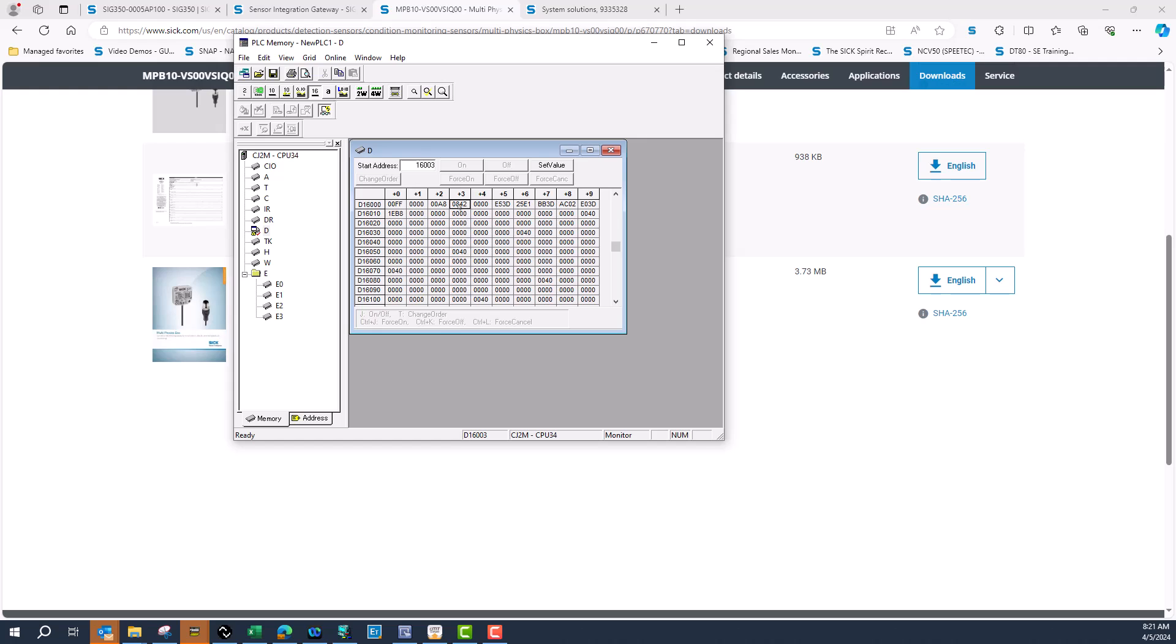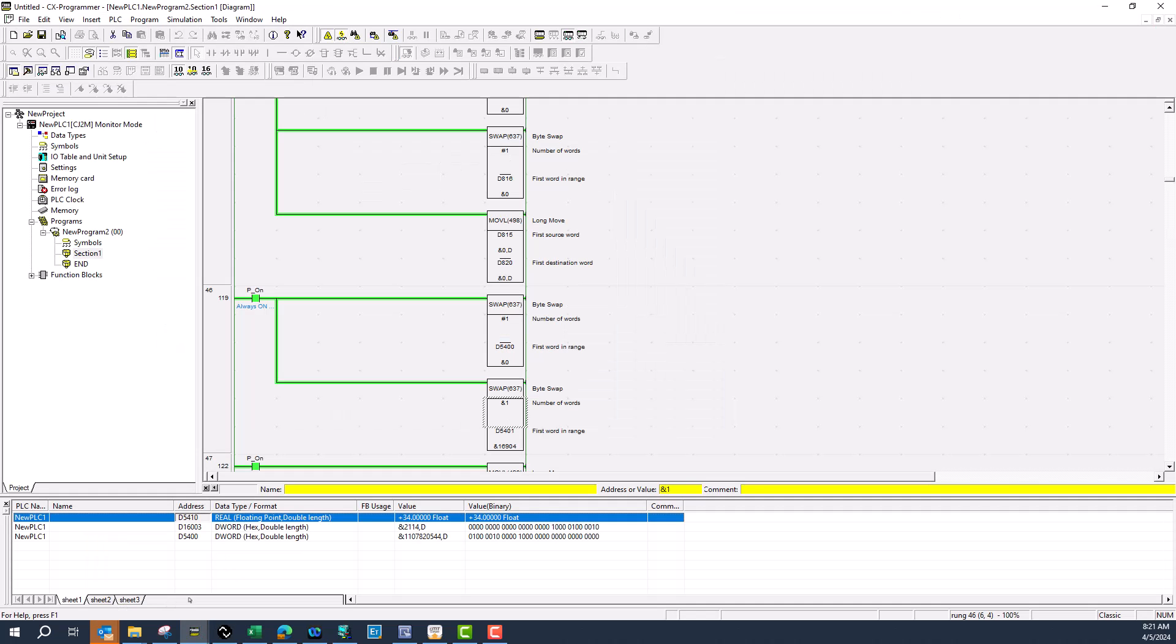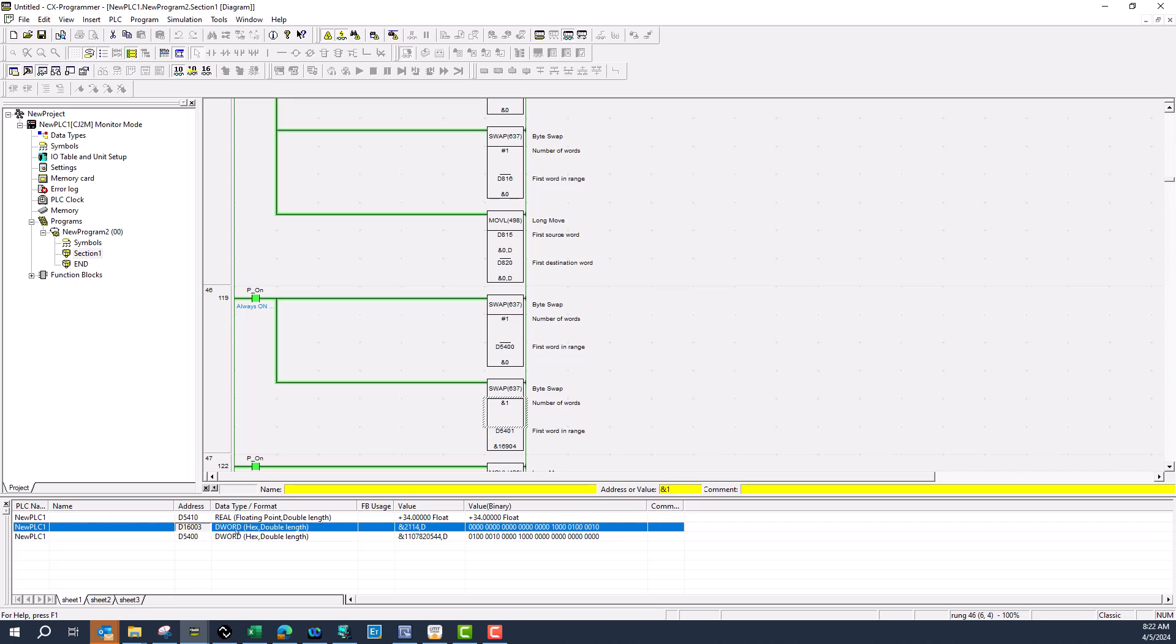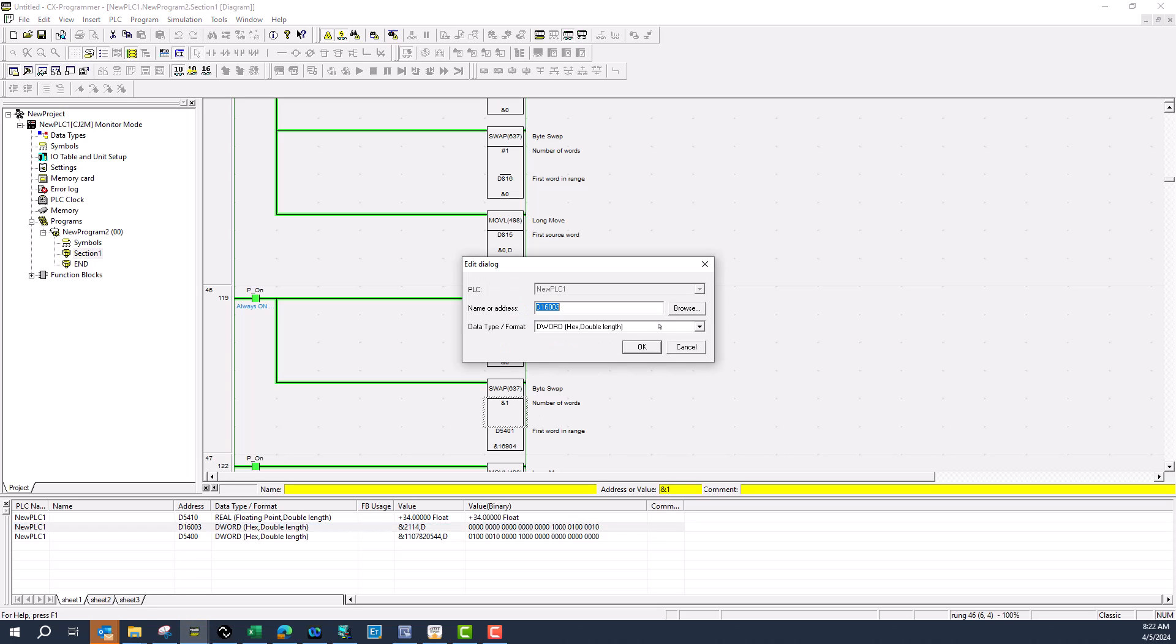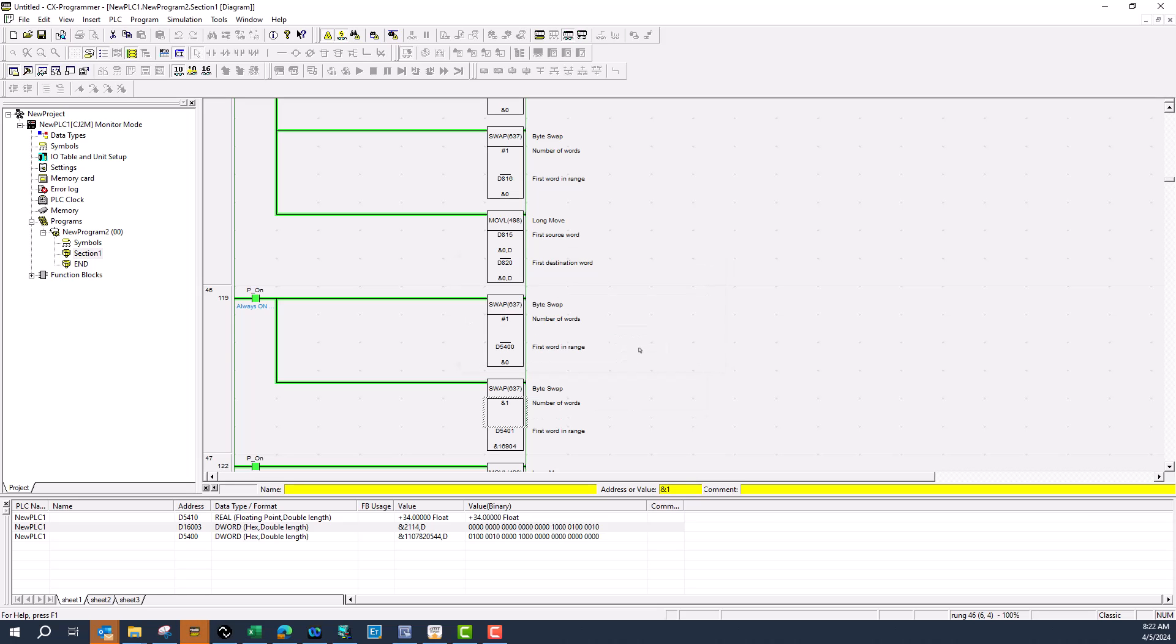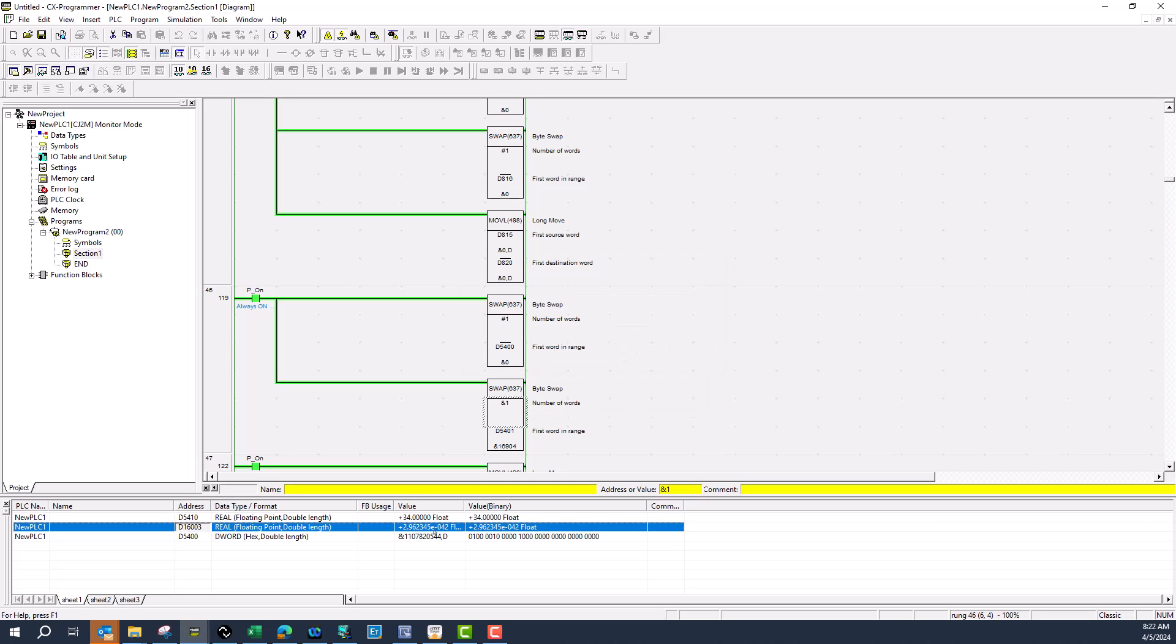If we look here, those are those two words: d16003 and d16004. Now at this point, if I start with d16003, you see here this is unusable data. Even if I turn this into a float, it still would not be good data. It says 2.9 when I'm actually at 34 degrees Celsius.